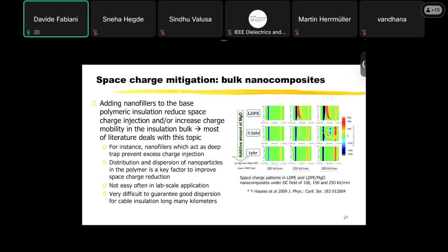I'll show you a few examples of these nanomaterials that can be used to reduce space charge. For instance, we can add nanofillers to the base polymeric insulation and try to reduce space charge injection or increase the mobility of charge in the insulation bulk, because this way we can avoid heterocharge accumulation. The example you see here, used for some Japanese cable for HVDC, uses magnesium oxide.